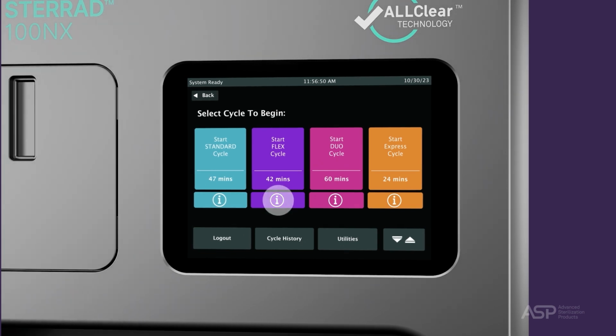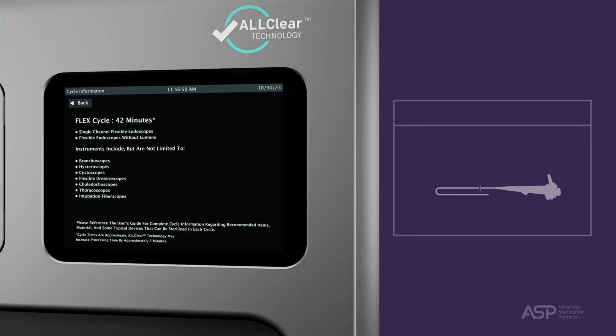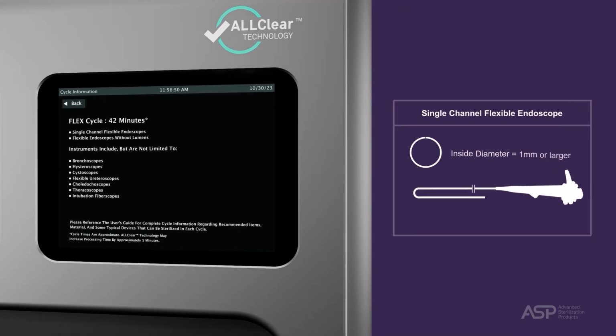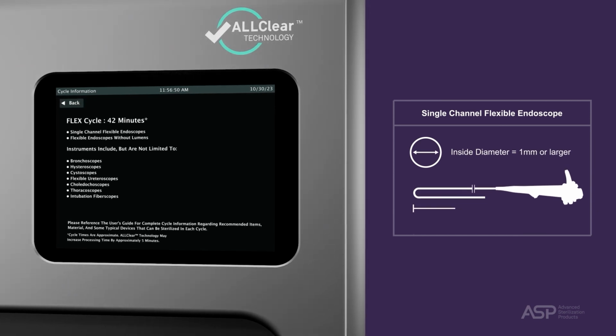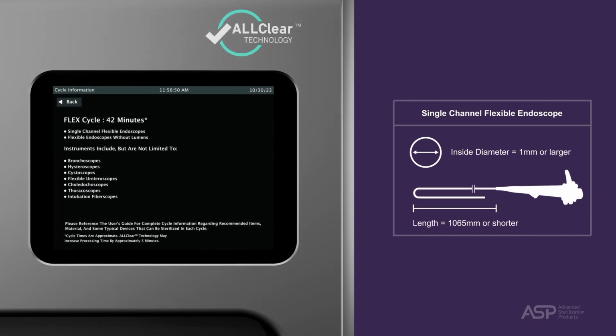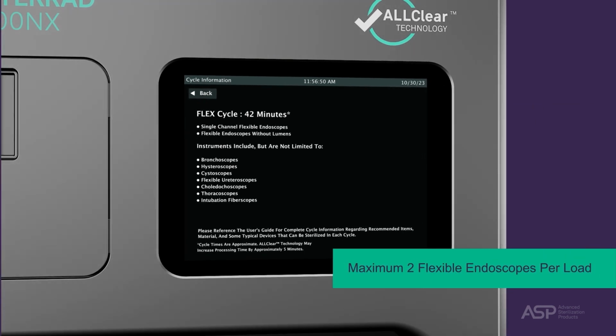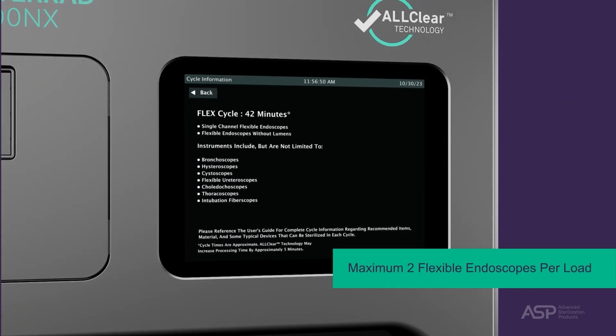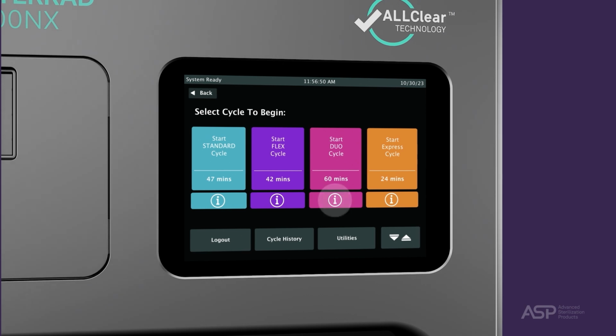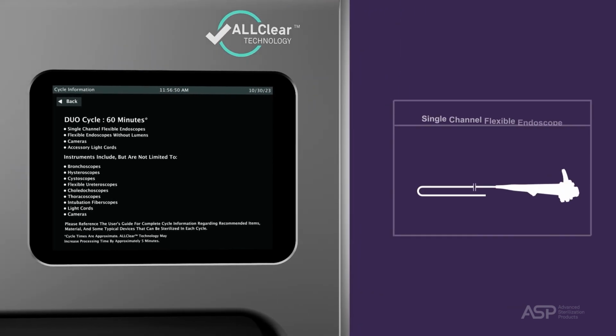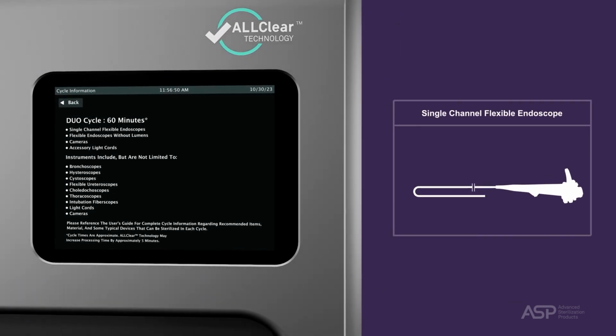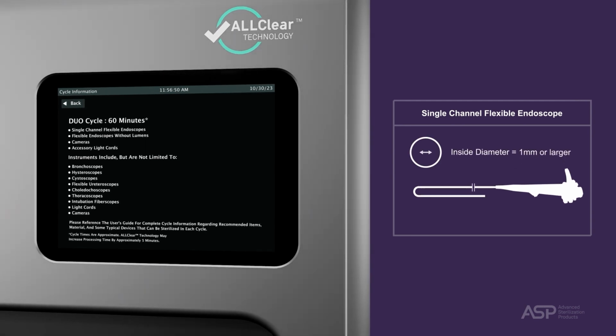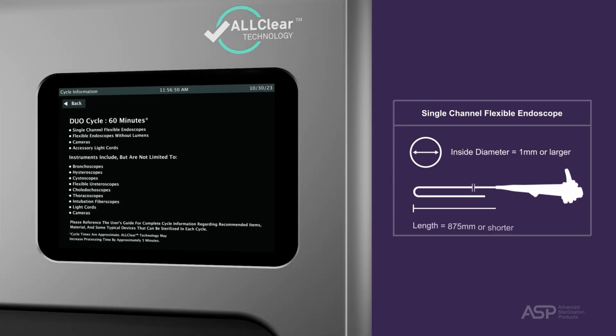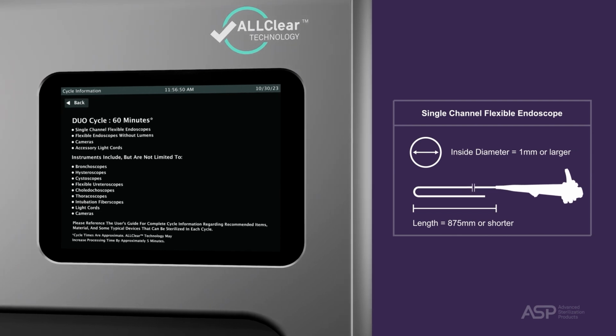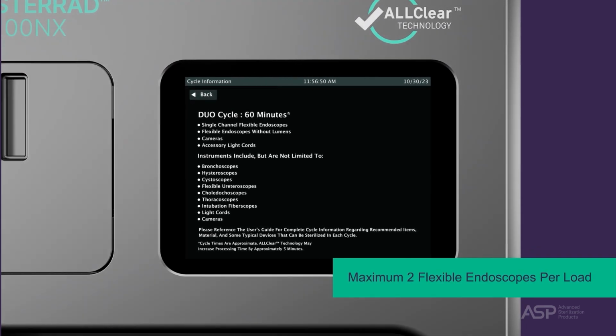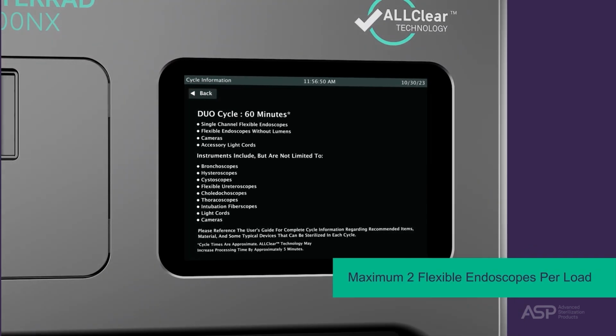The flex cycle is 42 minutes and should be selected for single-channel flexible endoscopes with an internal diameter of 1 millimeter or larger and a length of 1,065 millimeters or shorter. A maximum of 2 flexible endoscopes can be processed per load. The duo cycle is 60 minutes and should be selected for medical devices such as light cords and cameras and flexible endoscopes with an internal diameter of 1 millimeter or larger and a length of 875 millimeters or shorter. A maximum of 2 flexible endoscopes with light cords can be processed per load.